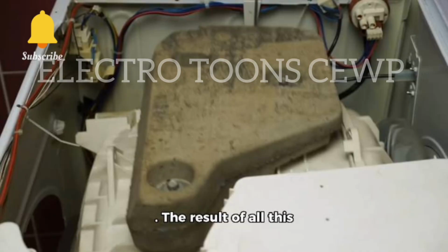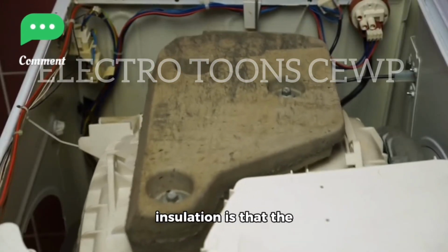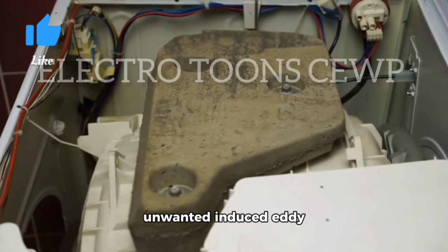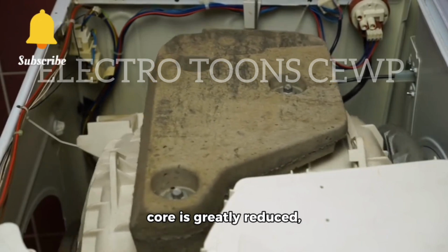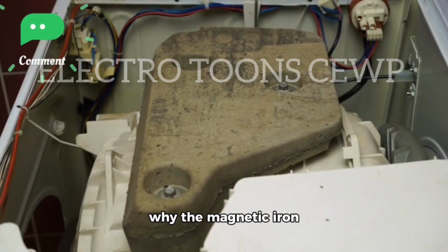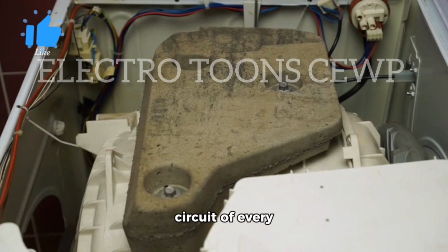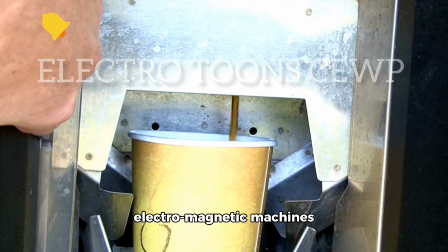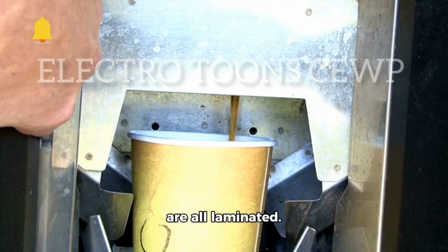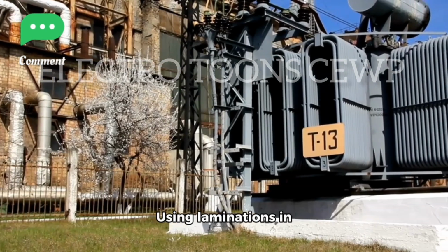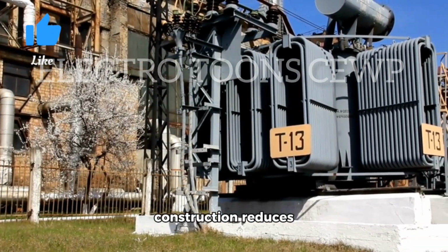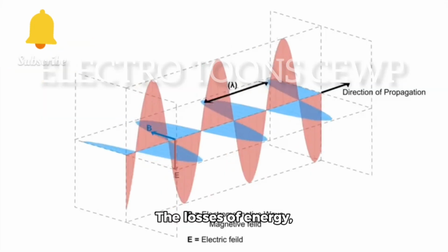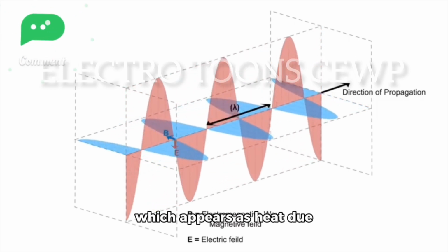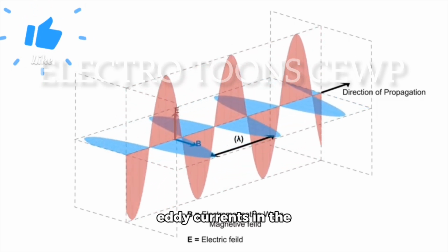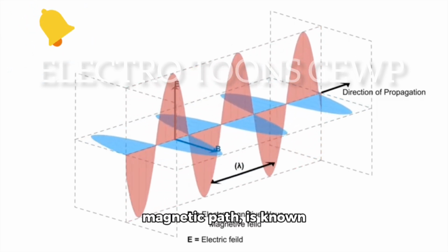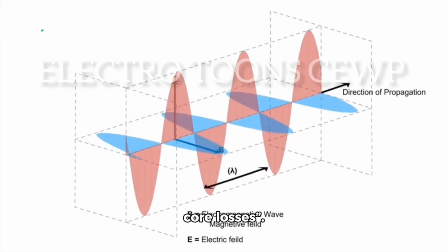The result of all this insulation is that the unwanted induced eddy current power loss in the core is greatly reduced, and it is for this reason why the magnetic iron circuit of every transformer and other electromagnetic machines are all laminated. Using laminations in a transformer construction reduces eddy current losses. The losses of energy, which appear as heat due both to hysteresis and to eddy currents in the magnetic path, is known commonly as transformer core losses.